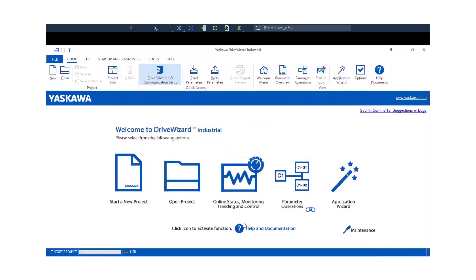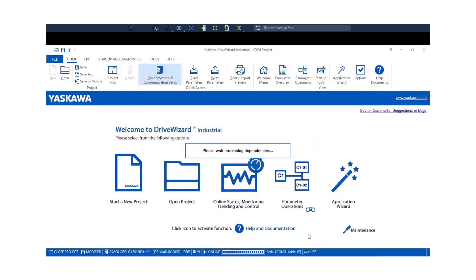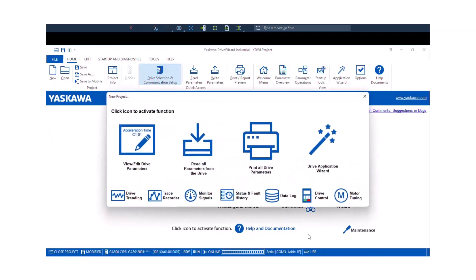Now it's also important to note that you cannot have simultaneous USB connections by DriveWizard Z and DriveWizard Industrial. You'll have to disconnect from one program to connect the other. Right now it's going to read all of the parameters and initialize the program to line up with the parameters for the size drive it is connected to. And you get this little shortcut screen here.